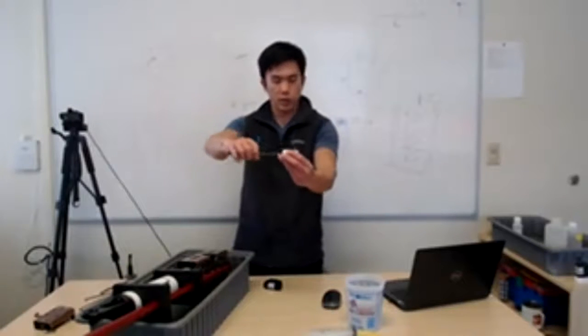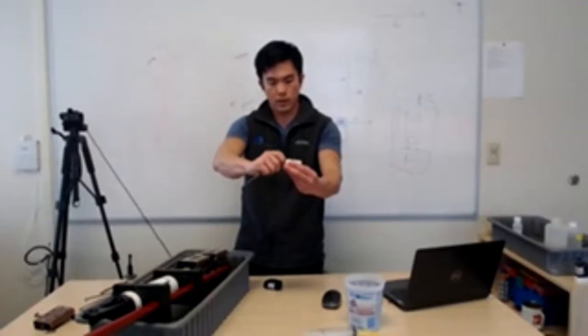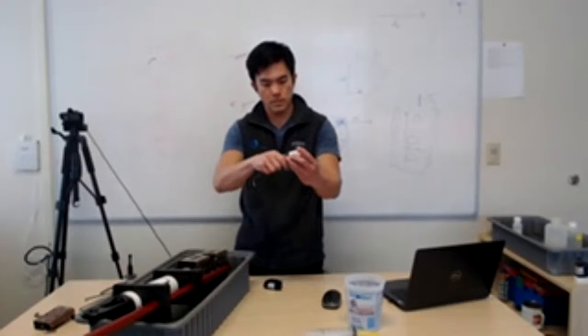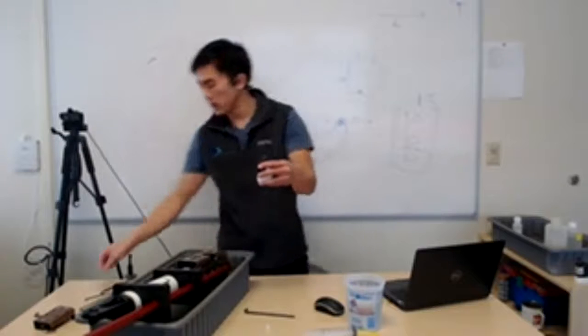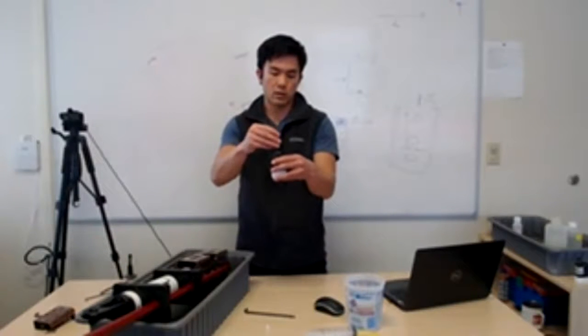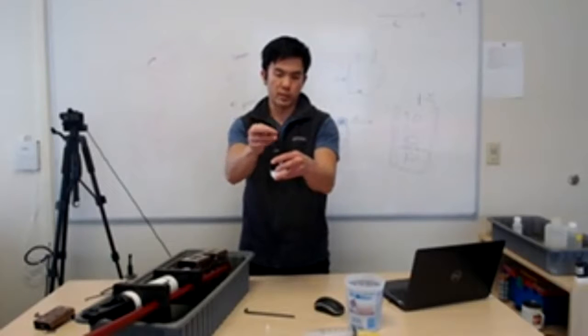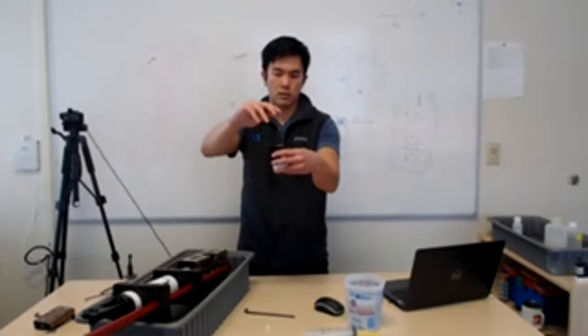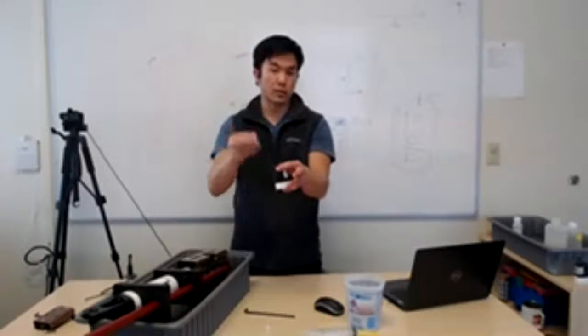Okay, so again, I'm just going to reverse what we did before, installing this pH sensor into the soaker block. The first thing I like to do is remove the screw that blocks off the reservoir to the potassium chloride spot. Take that out, don't lose it. Then I'm going to ensure that my connector is clean, make sure there's nothing bridging the O-ring, make sure it's dry. I'll insert it into the soaker block like that, and carefully screw this in place, gently twisting it between my fingers until it's snug, making sure not to over tighten.